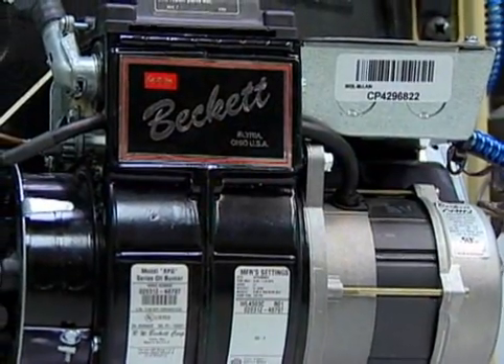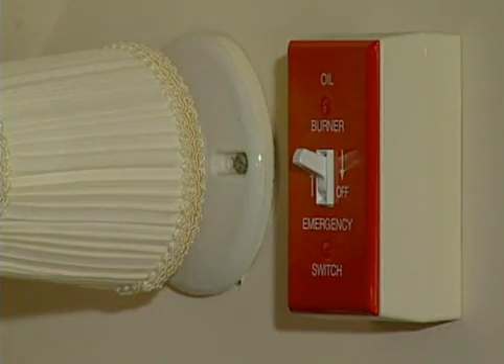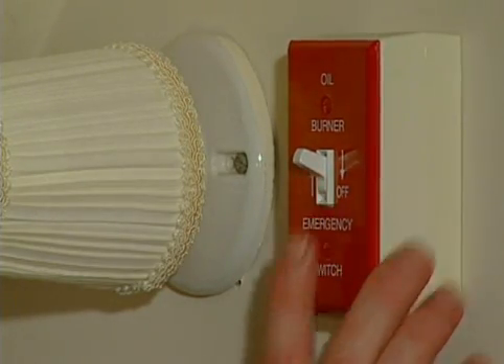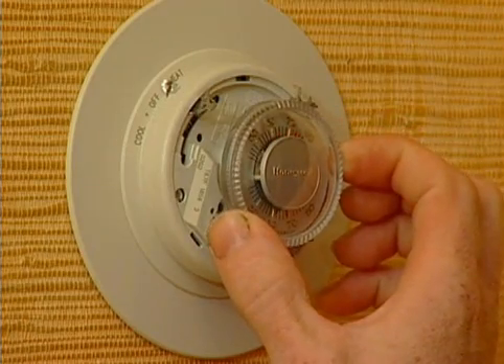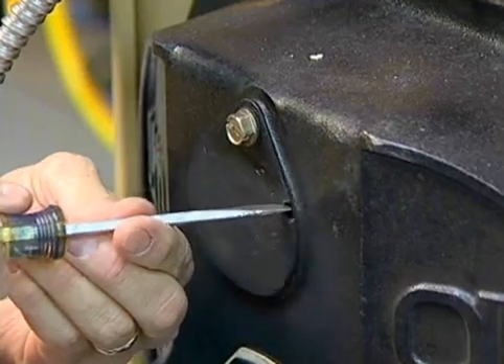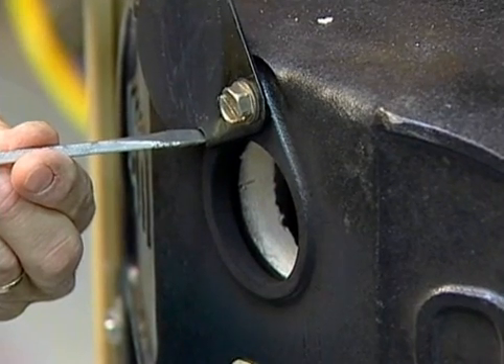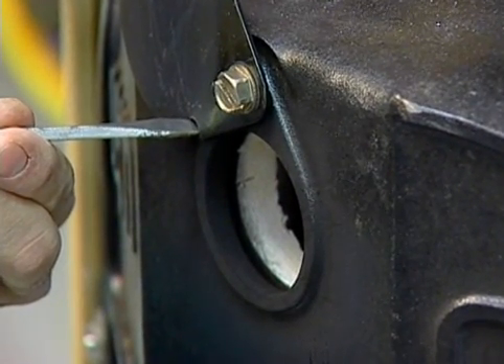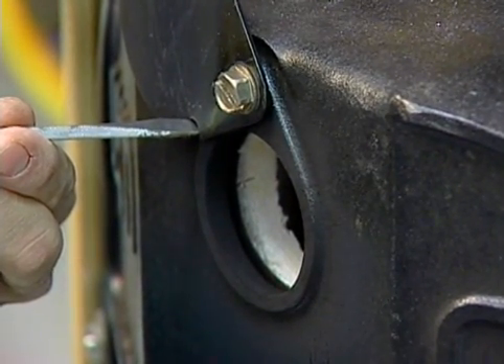Let's use the example of an oil burner that won't start. Normally, an experienced service technician will first ask the customer about the situation and listen closely to their responses. Be sure to ask if they've pressed the reset button and advise them that it should never be pressed more than once. Then verify that electrical switches are in the on position and that the thermostat is set above room temperature. Check to be sure that there is not a fire burning in the chamber. Now you're ready to check the primary control.